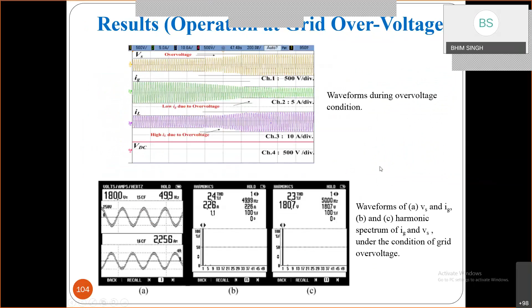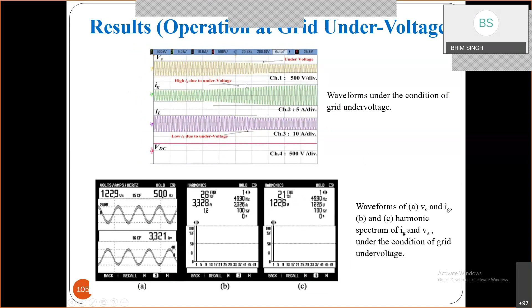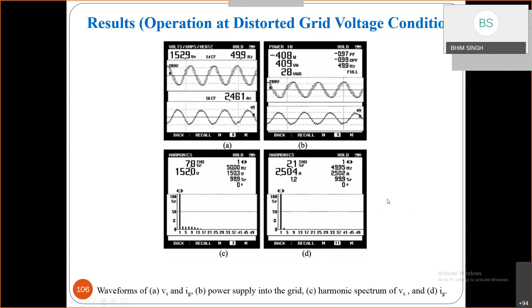This is typical operation under voltage, which is very common in India. The load and power consumed are affected by that, but we modified the control in a manner that it works under under voltage, over voltage, and all those conditions. Even when there is distortion in the grid voltage, say a voltage THD of 7.8%, the grid current THD reduces to 2.1%. So we are able to inject current at unity power factor with less THD compared to the voltage. The control is modified so that even with distorted voltage the system works, where the distortion may be because of some other load, not because of the solar generation. The impression given was that solar inverters really pollute the grid. But we say solar inverters do not pollute, they can improve the grid. We have to prove it the reverse way.